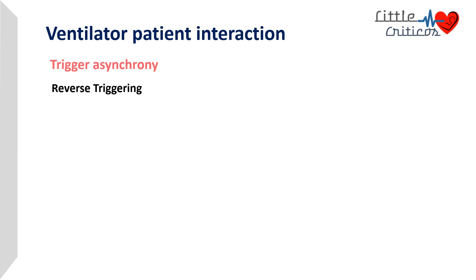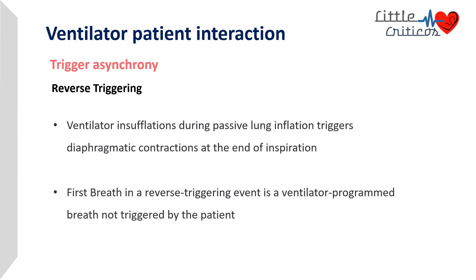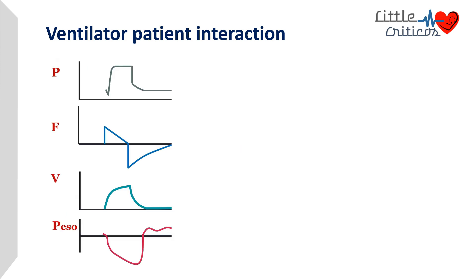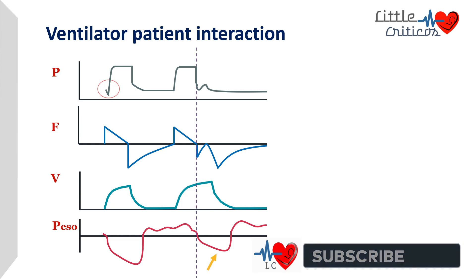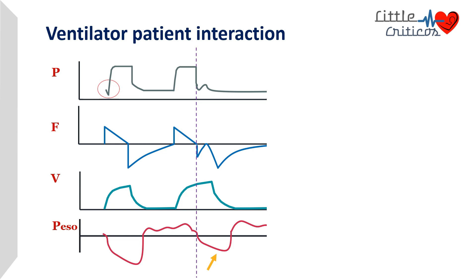Reverse triggering is a type of trigger asynchrony that is incompletely understood but increasingly recognized. The ventilator insufflation during passive lung inflation triggers diaphragmatic contraction at the end of inspiration. The first breath in a reverse triggering event is a ventilator-programmed breath, not triggered by the patient. In pressure-control mode, one can observe that at the end of inspiration, diaphragmatic contraction occurs, resulting in scooping of the flow loop towards the baseline and a slight increase in pressure.